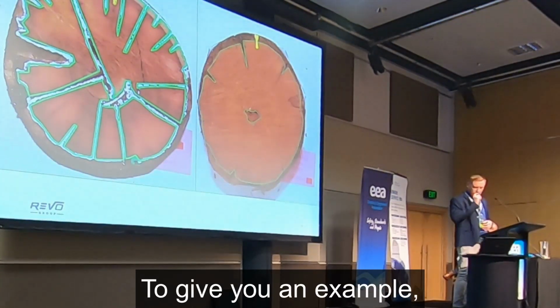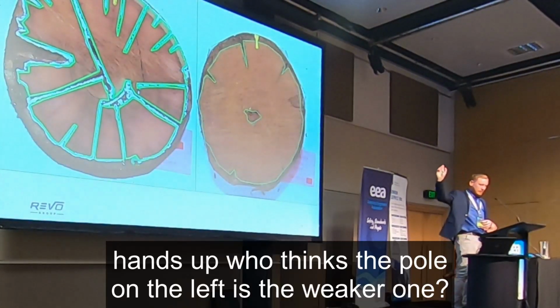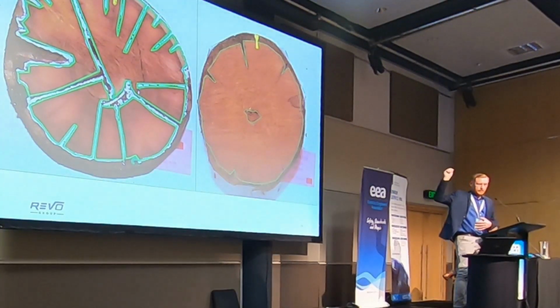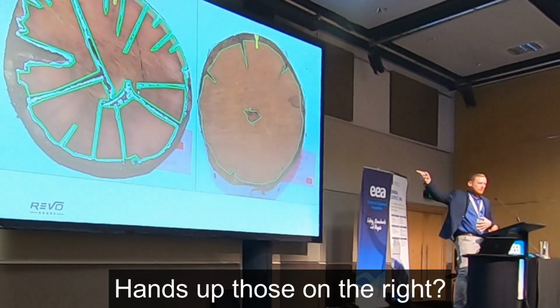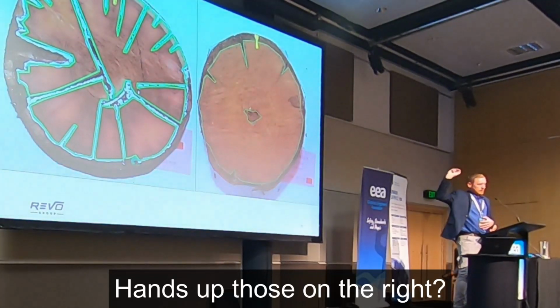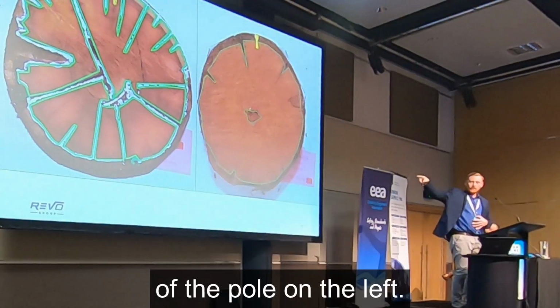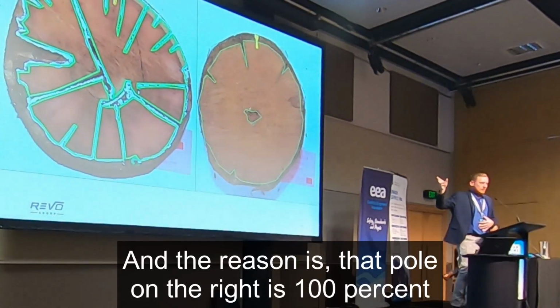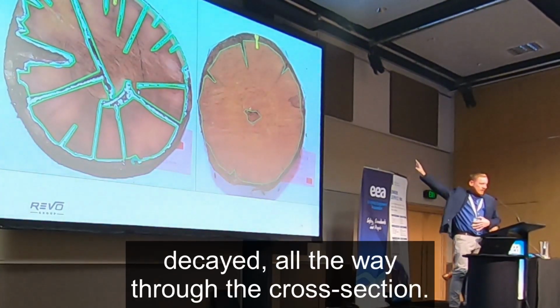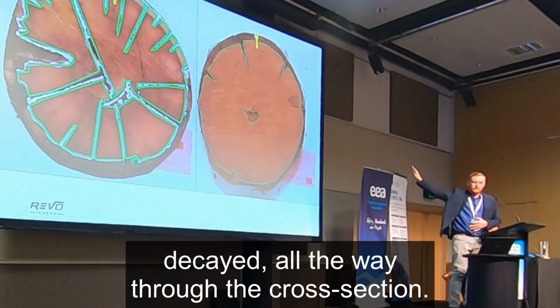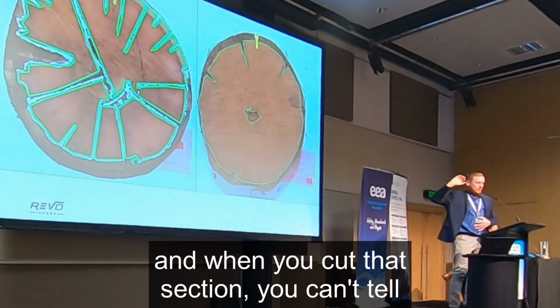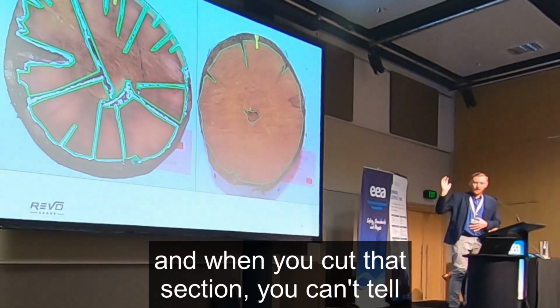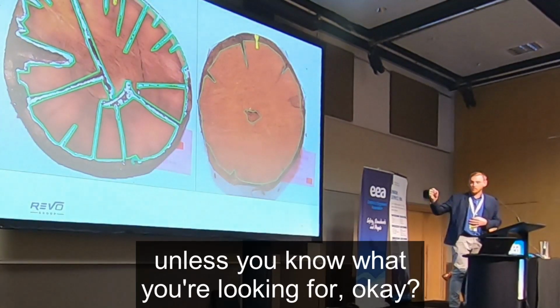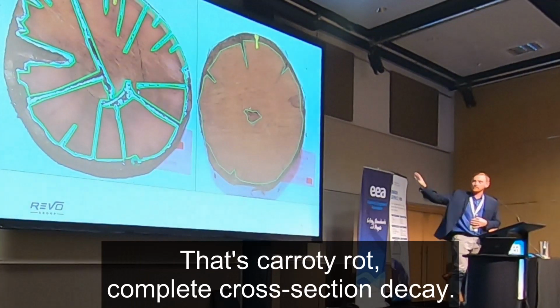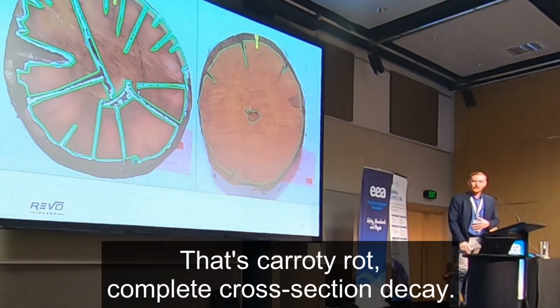To give you an example, hands up who thinks the pole on the left is the weaker one. Okay? Hands up those on the right. The pole on the right is actually half the strength of the pole on the left. And the reason is, that pole on the right is 100% decayed all the way through the cross section. Okay? Doesn't look like it, and when you cut that section, you can't tell unless you look at the shavings, unless you know what you're looking for. Okay? That's carroty rot, complete cross section decay.